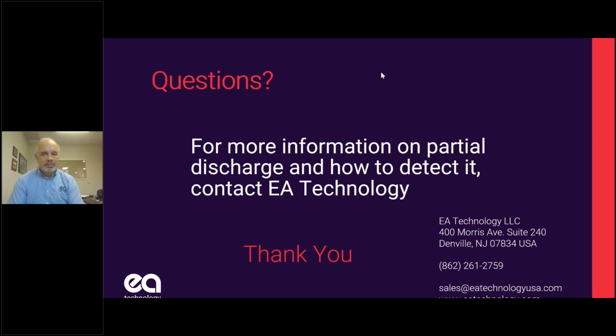Going back to that earlier question about the severely damaged shield, the NETA spec recommends a shield continuity test. Yes, definitely do a common shield continuity test if you have any concerns about the quality or condition of the shield.